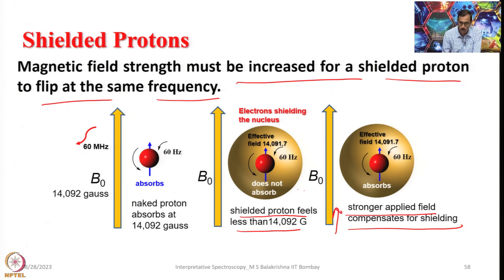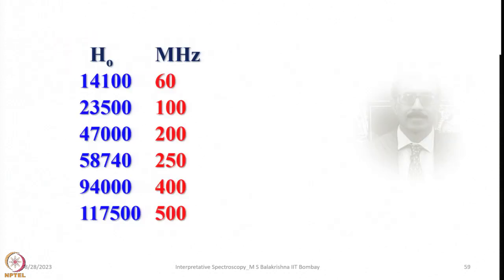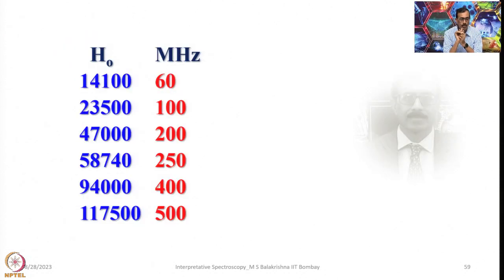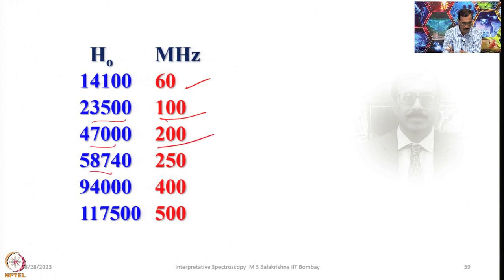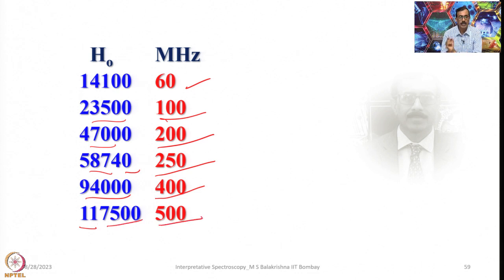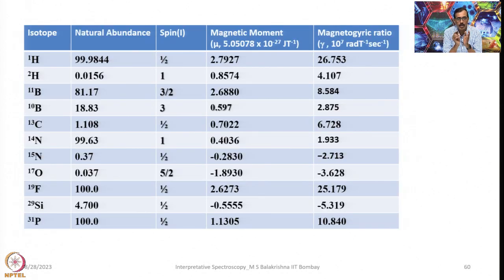The Larmor frequency corresponds to different field strengths. For proton: at 14,100 gauss it is 60 megahertz; at 23,500 gauss it is 100 megahertz; at 47,000 gauss it is 200 megahertz; at 58,700 gauss it is 250 megahertz; at 94,000 gauss it is 400 megahertz; and at 117,500 gauss it is 500 megahertz. This slide shows the different field strengths and corresponding Larmor frequencies.